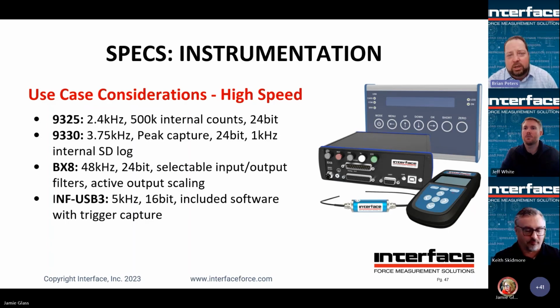24 bits of high resolution, and you have full selectable filters, input output, and then active output scaling. So you can actually define what you want the output channels to scale to, as well as defining what filtering you want on that. So keep in mind, again, with a high-speed application, make sure the settings are set right and you're actually seeing what you think you are.